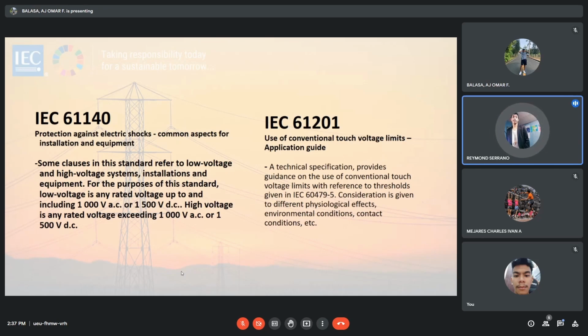IEC 61140, protection against electric shock, common aspects for installation and equipment. Some clauses in this standard refer to low voltage and high voltage system installations and equipment. For the purpose of this standard, low voltage is any rated voltage up to and including 1000 volts AC or 1500 volts DC, and high voltage is any rated voltage exceeding 1000 volts AC or 1500 volts DC.